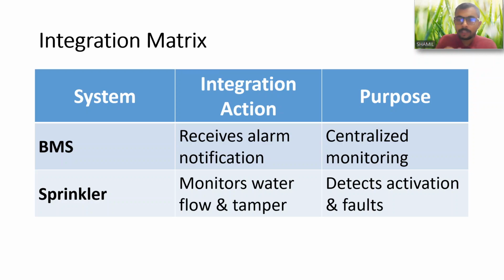I will repeat once again for the sprinkler system. If there is any water flow movement, or any tampering of the valves or switches, in both cases a signal will be sent to the fire alarm control panel. Normally, if there is a water flow movement, an alarm signal will be provided to the fire alarm control panel. And if there is any tampering of the switches, a supervisory signal will be sent to the fire alarm control panel.